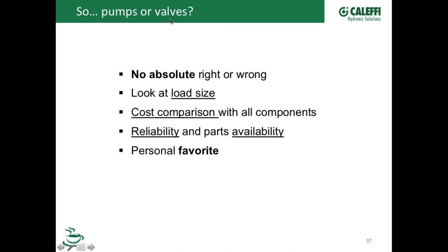So again, how do I decide which to use? There is typically no right or wrong. Some guys will look at the load size. They say, if it's under 150,000 BTU, I can easily move 12 gallons a minute with a single, simple, off-the-shelf little wet rotor circulator. That's how I decide. If I've got a 200,000 BTU boiler, I'm probably going to need more than one pump, or I'm going to be getting into a bigger, higher-priced pump. So you can look at it that way.